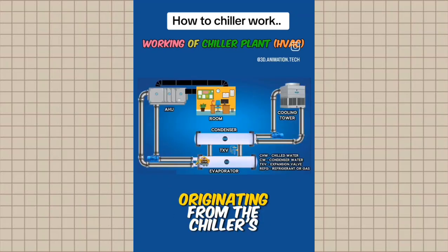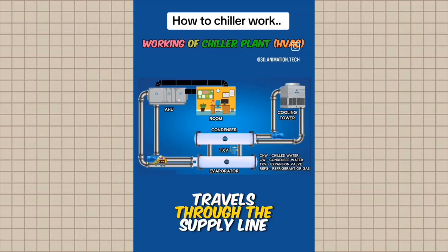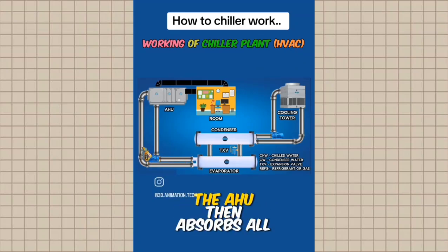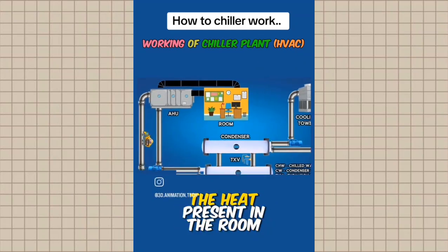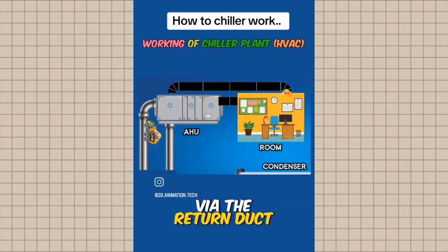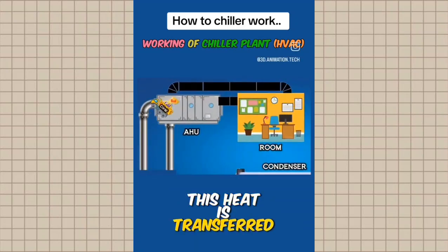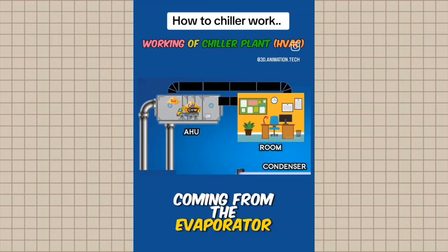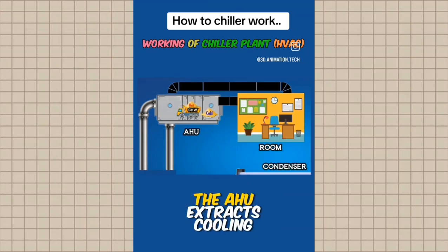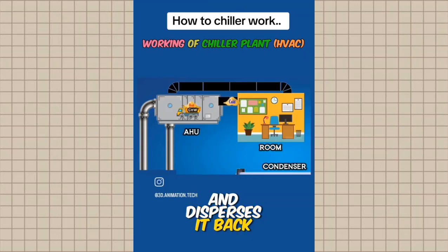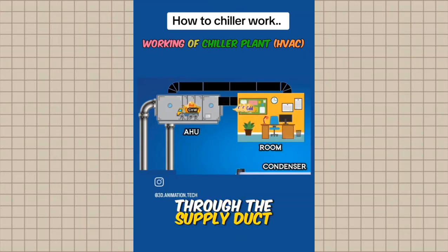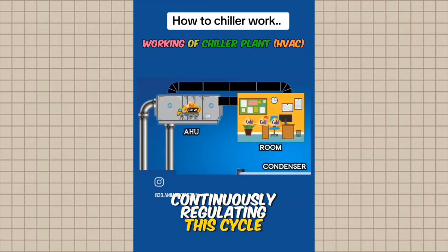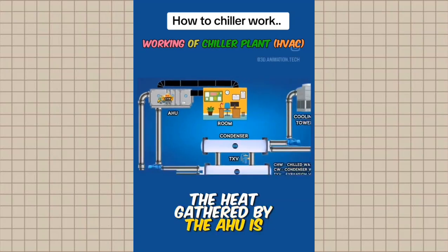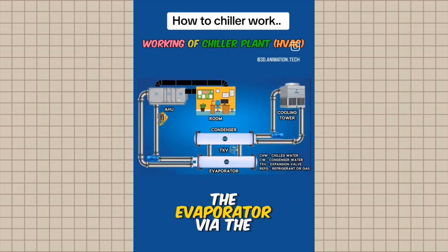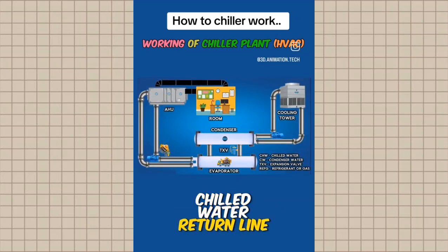Chilled water originating from the chiller's evaporator travels through the supply line to the AHU. The AHU then absorbs all the heat present in the room via the return duct. This heat is transferred to the chilled water coming from the evaporator. Subsequently, the AHU extracts cooling from the chilled water and disperses it back into the room through the supply duct, continuously regulating this cycle. The heat gathered by the AHU is conveyed back to the evaporator via the chilled water return line.